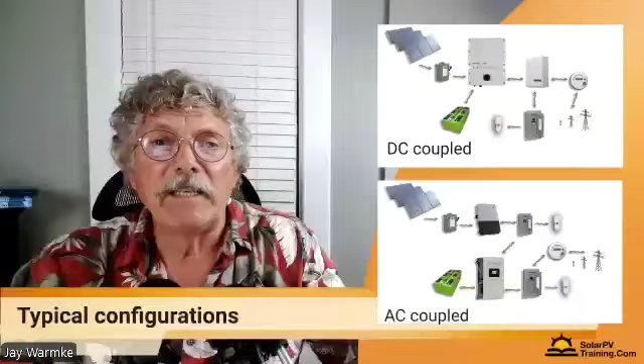One power source is bidirectional to your battery. There could be an auto transformer built into the inverter or as a separate unit, and some sort of auto disconnect, because your system has to disconnect from the grid if the grid goes down - you don't want to be feeding power onto the grid when it's no longer functioning, known as islanding.